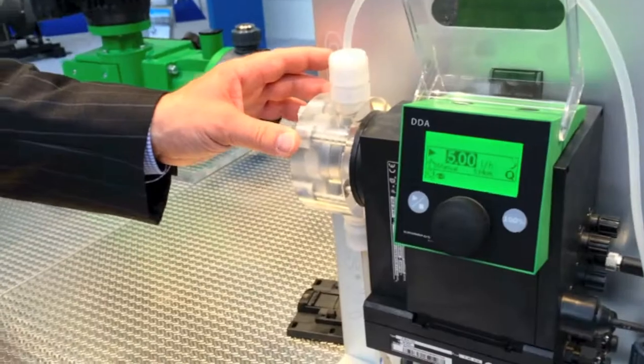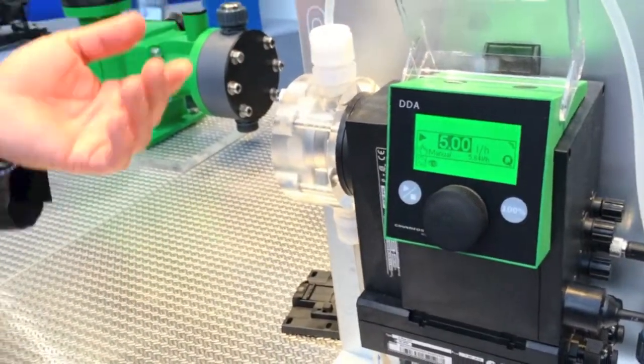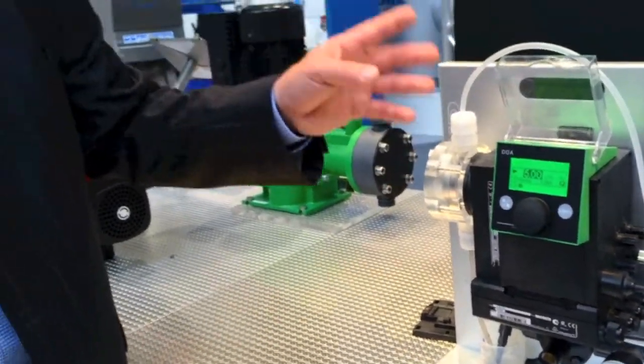So our Smart Digital pump has a dosing monitoring system. It can detect specific failures in the dosing process. In other pumps, if there is a failure, you get an alarm, and then you have to check the whole pump to find the problem. You have to disassemble the valves and clean them, and it's trial and error. With our Smart Digital, the pump can detect exactly, for example, that there is a leakage in the discharge valve. You can repair it, and the pump is back in operation in a very short time.